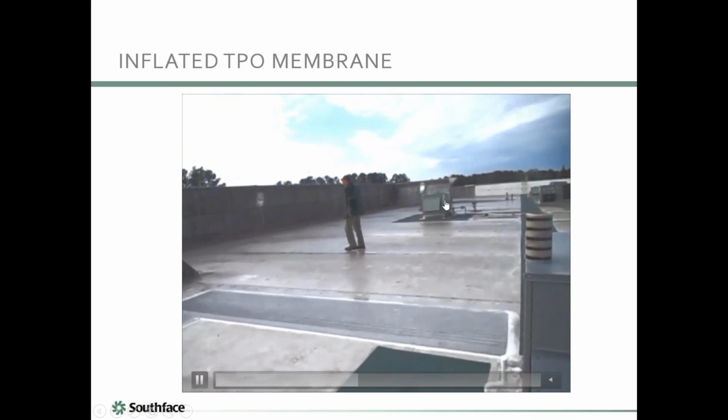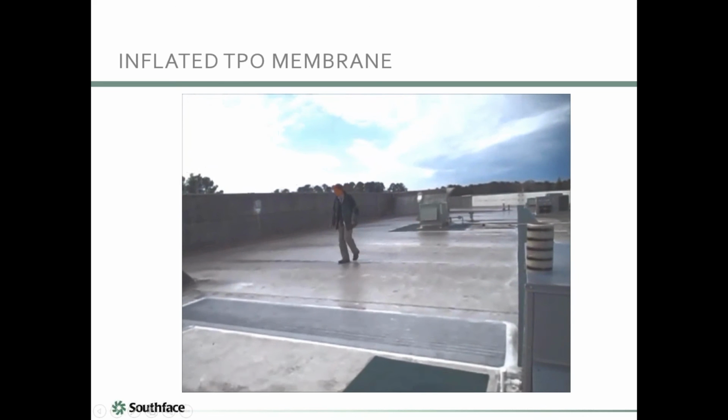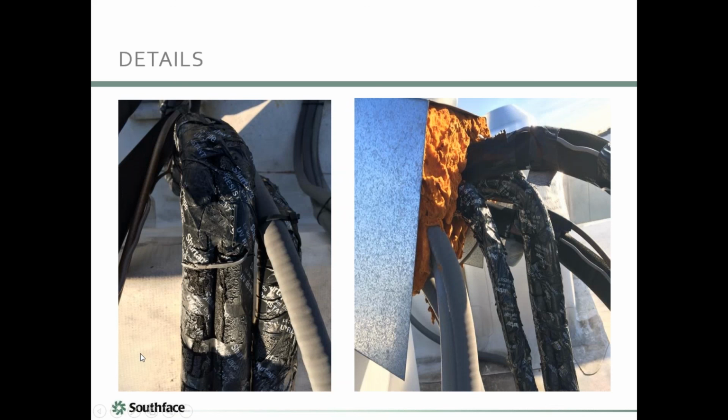What is that? Again, just mechanical penetration, stuff that runs from inside to outside. And here we're looking at some pictures of various attempts to seal or not such penetrations. We saw a lot of that too, where it was just no sealing, not even an attempt. And when you had particularly split systems with a condensing unit on the roof, the refrigerant lines and electrical lines and thermostats and stuff had to get through. So, and this is a classic leak pathway.